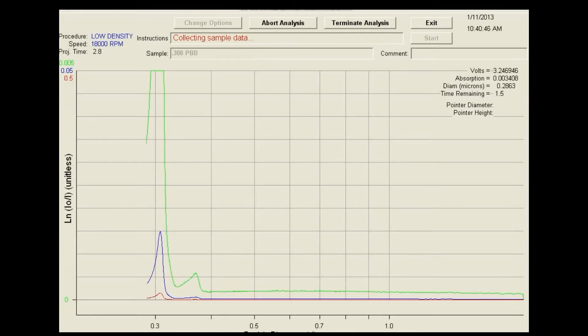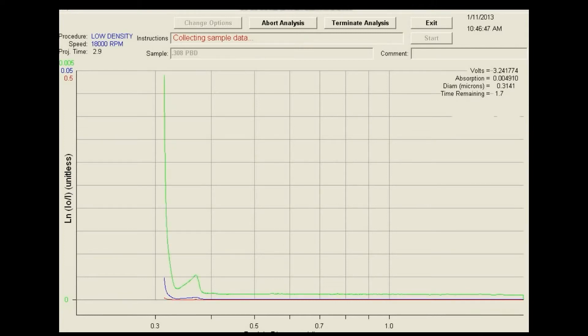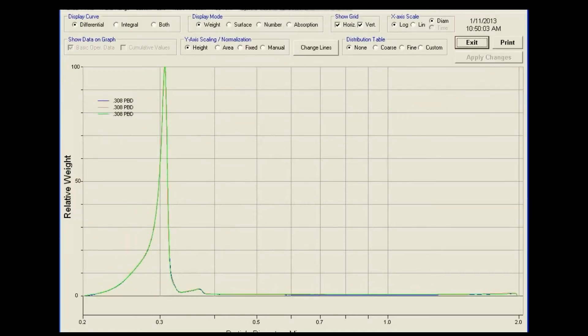The CPS disc centrifuge allows the measurement of highly polydispersed particles within an approximate size range of 3 nanometers to 60 microns, depending on particle density. The CPS can measure particles with as little as 2% size difference from one another. Rather than relying on a predictive algorithm, the CPS physically separates particles and measures them as they pass a light source detector.